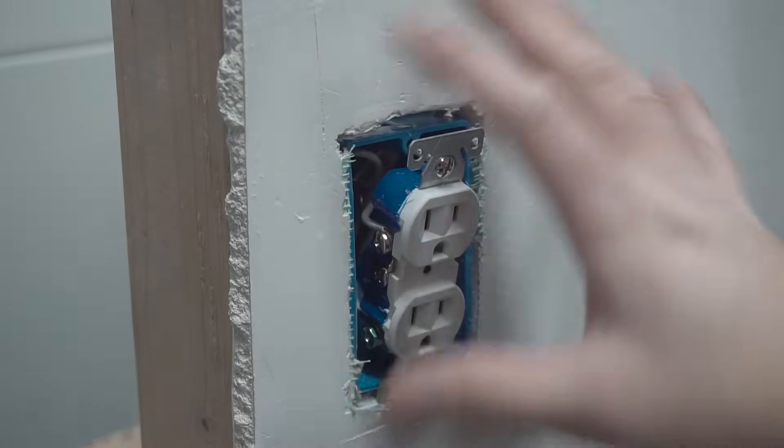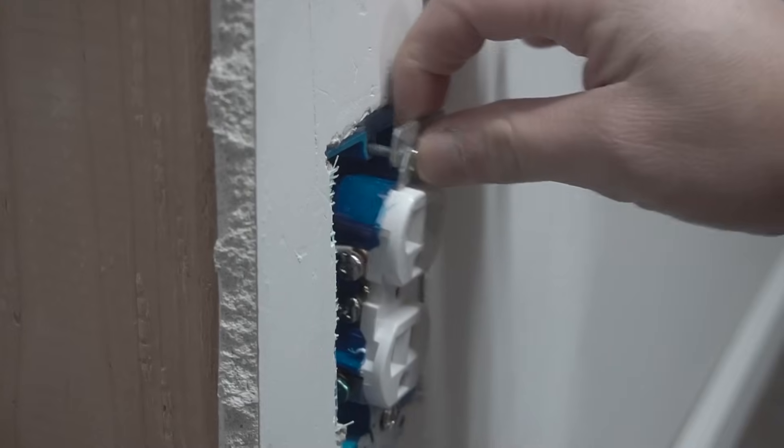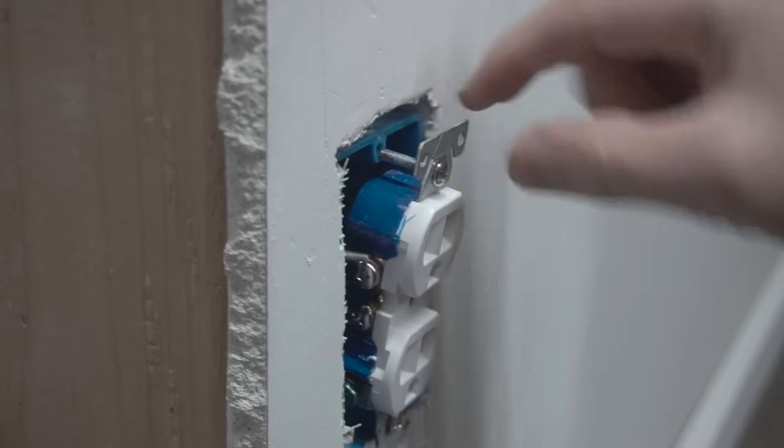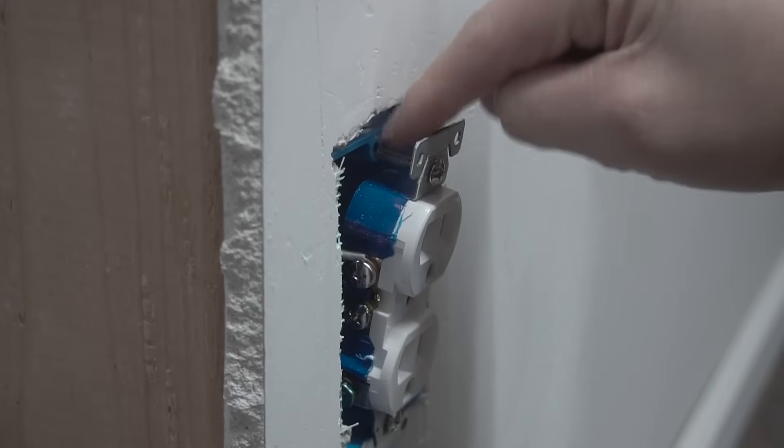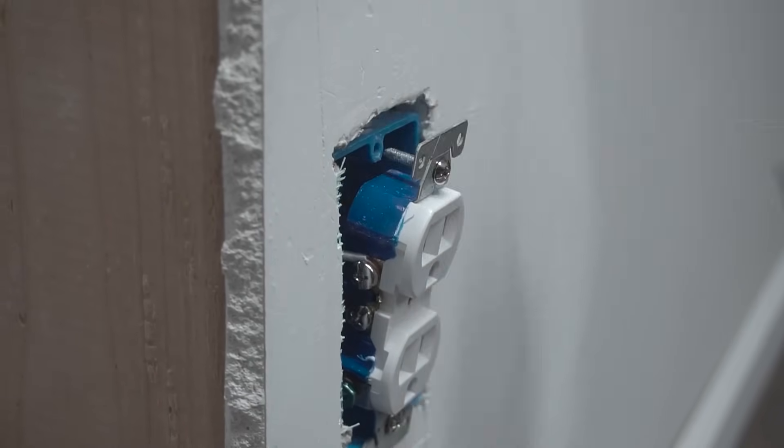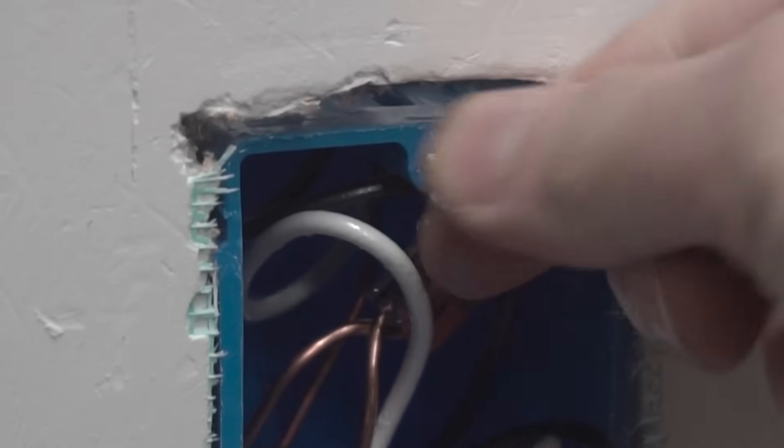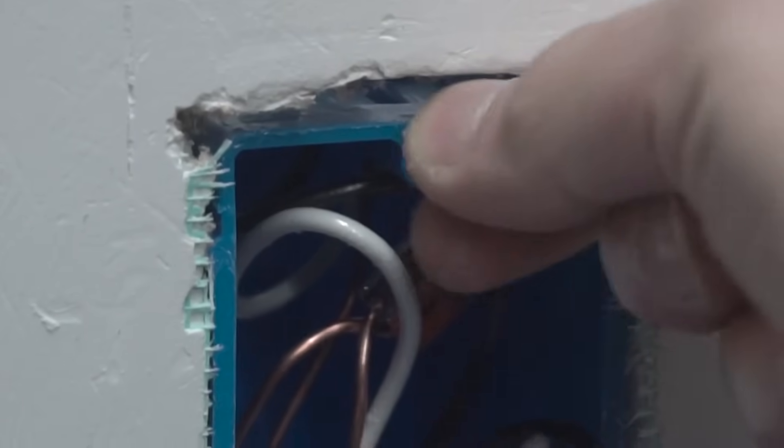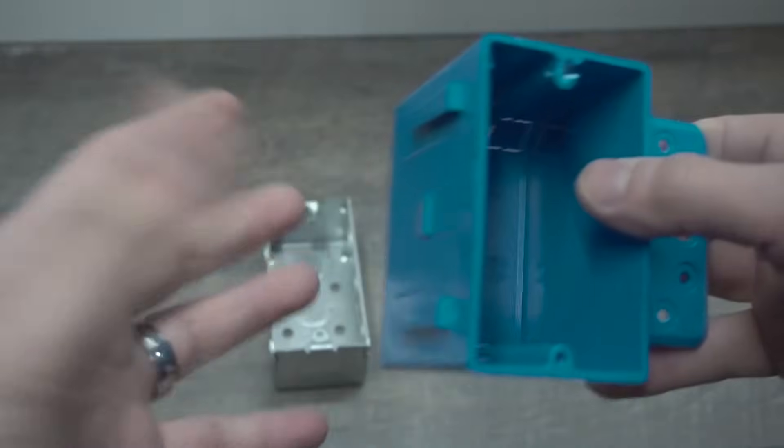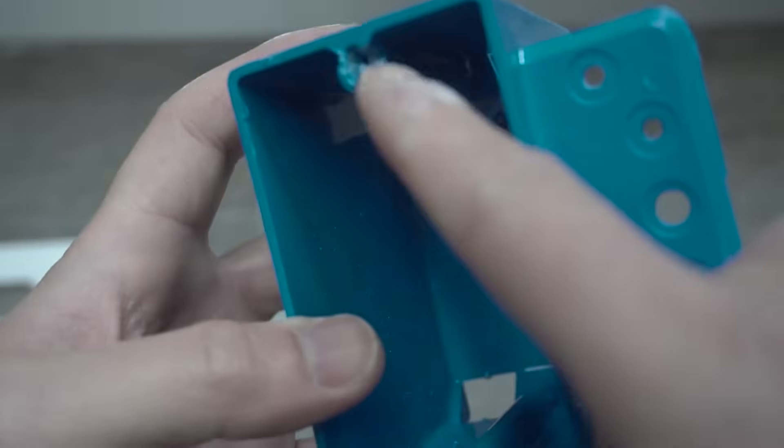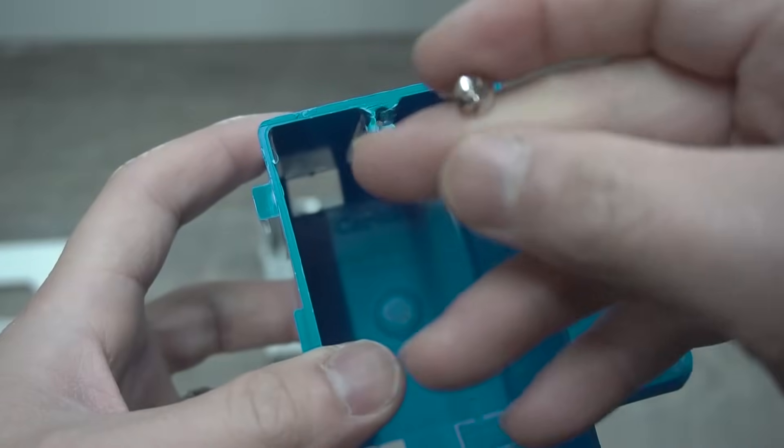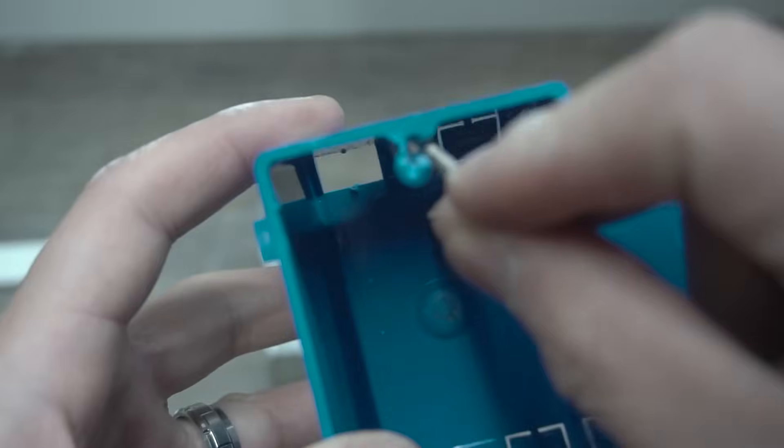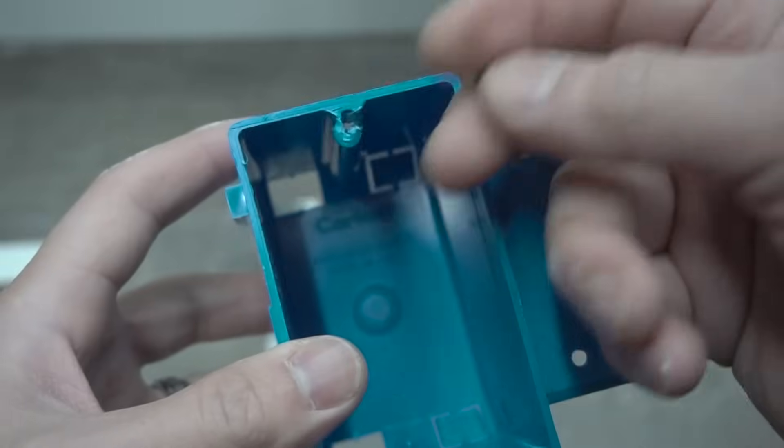This actually is just a mock-up. Nothing is really wired. As you can see, this is what's causing it not to attach to the J-Box or junction box or electrical box, whatever you want to call it. But it looks like the thread inside this J-Box is threaded out. Look at this inside thread of this J-Box. You can tell that it's really hollow and this thing is just wiggling in there. There's no resistance. That's scenario problem number one. Scenario number two is where you have an electrical box that the top part is damaged. So here is actually the screw that's coming from that receptacle or outlet and it's not going through because it's damaged, just like that.